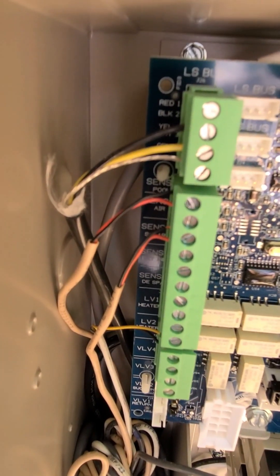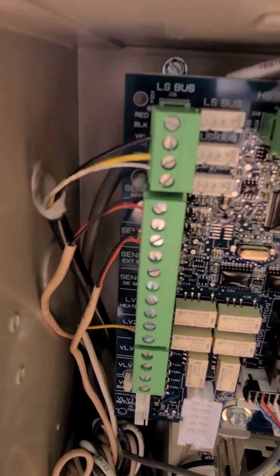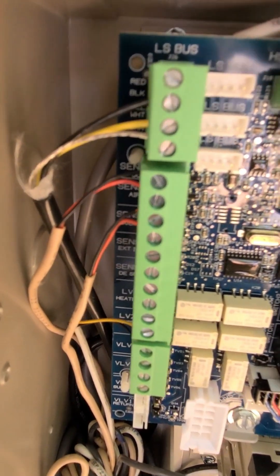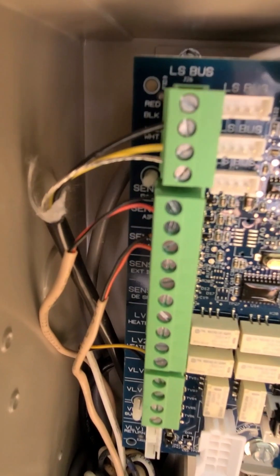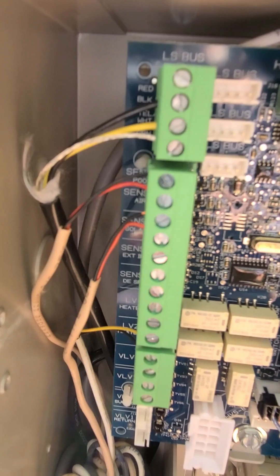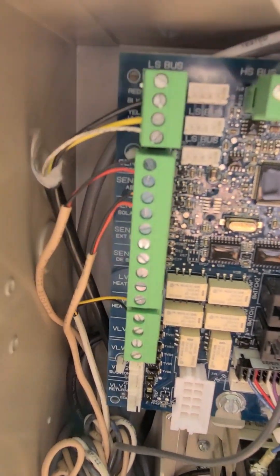Got that fixed — just had to do a little bit of work to get this to reach up here: cut it, restrip it, and put it on there properly. That's how it goes on this panel box, the Hayward OmniLogic. It goes the same way on the pump, and if you do that, it will communicate properly.